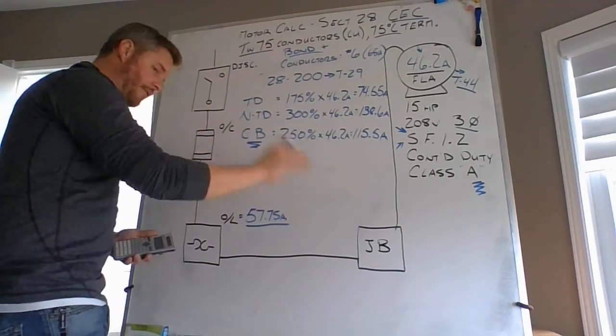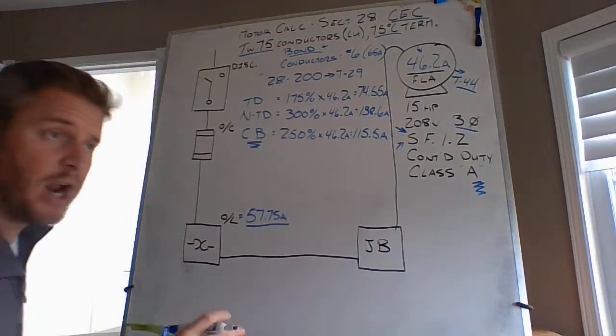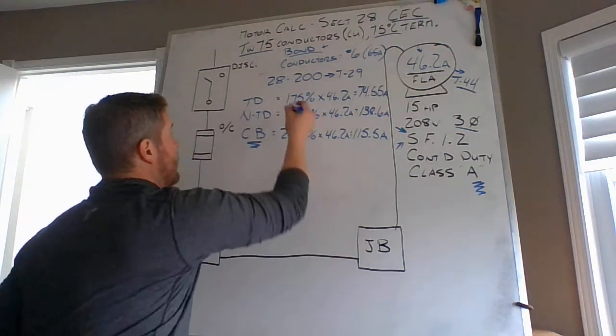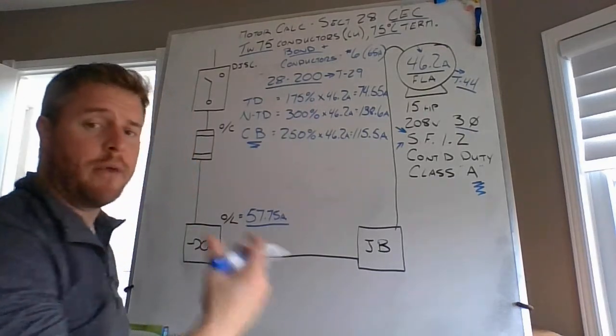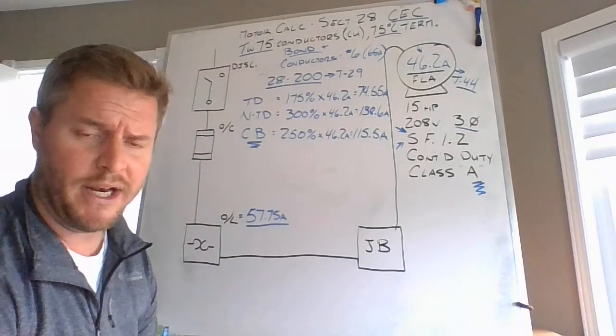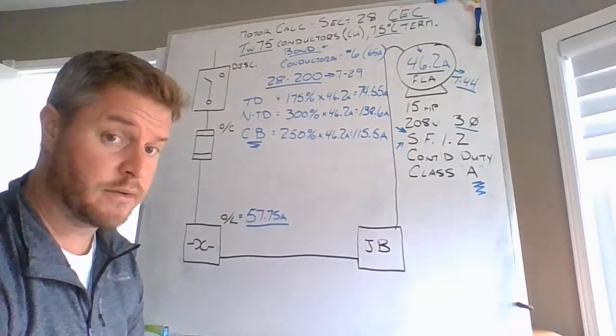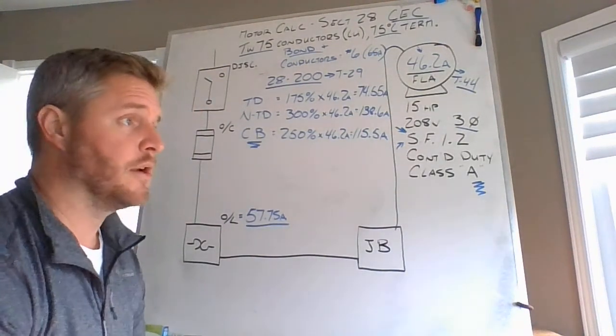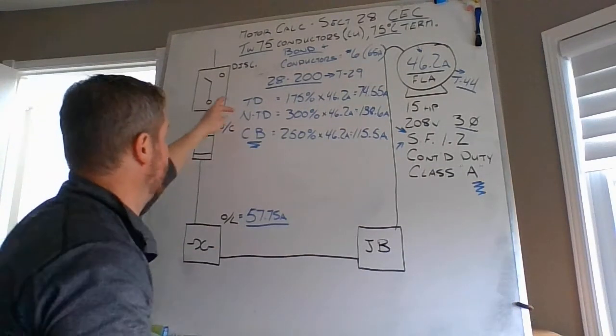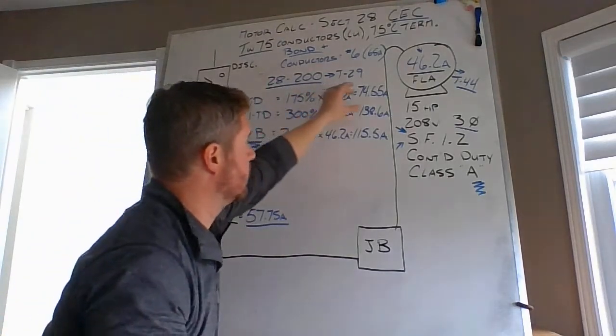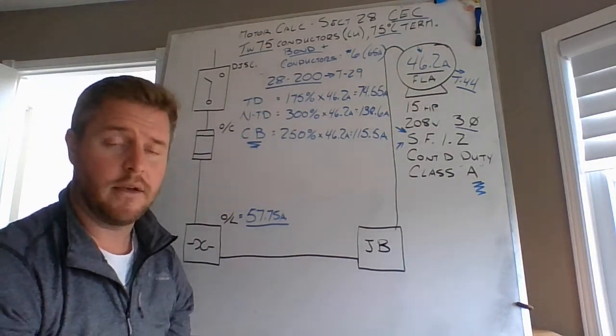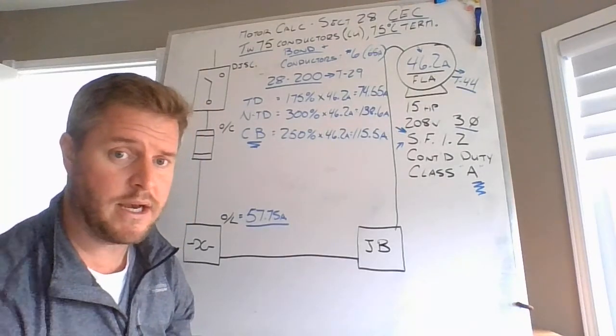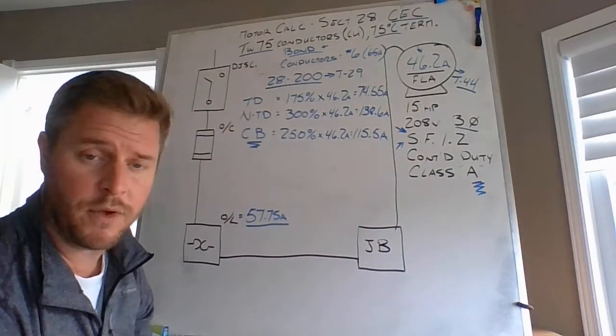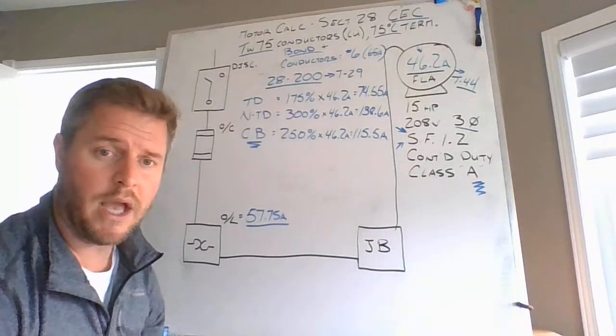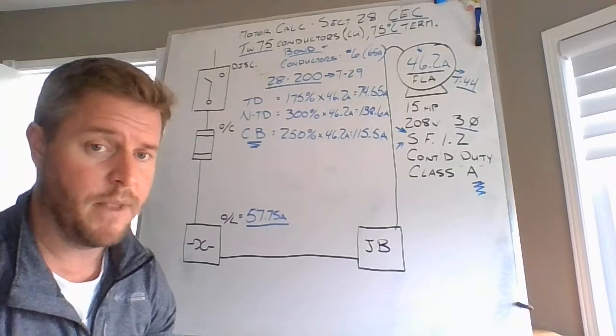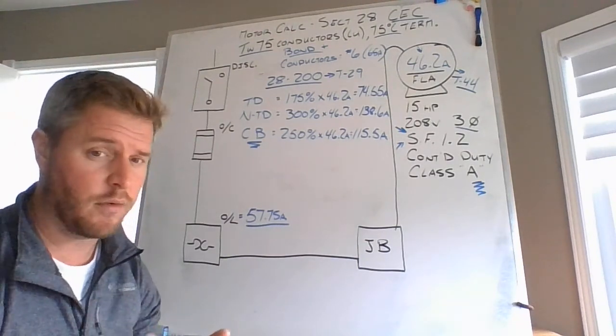Maximum calculated values. Maximum. I cannot exceed these values, and that is specifically stated for you in 28-200 when they refer you to Table 29. I cannot exceed these values. These are maximum calculated values. So if you have chosen a time delay fuse, you do this calculation and you call the wholesaler and you say, hey, what's up, guys? I need a 74.55 amp fuse. Can you put 3 of those on the counter? And I'll be there in about 20 minutes to come and pick those up. Only the 74.55 amp fuses, though.